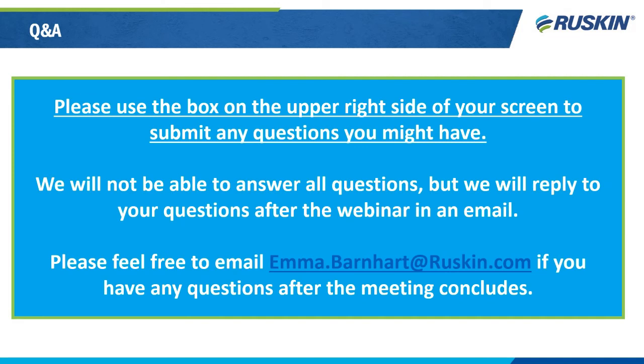So it looks like our first question is, I typically design standard louvers to have no more than 500 FPM free area velocity. What velocity can I use for wind-driven rain louvers? All right, Tessa, I'll take that one. This is James. Wind-driven rain louvers, you size them a little bit differently than a standard louver. Standard louver, you might pick 500 feet per minute as your design for a louver, no matter what model.